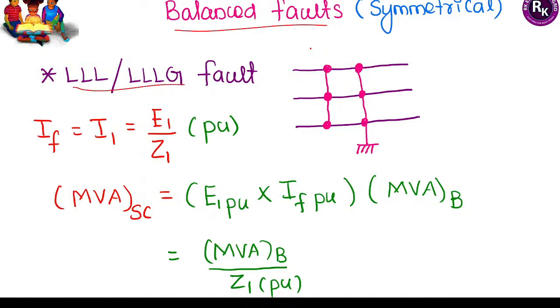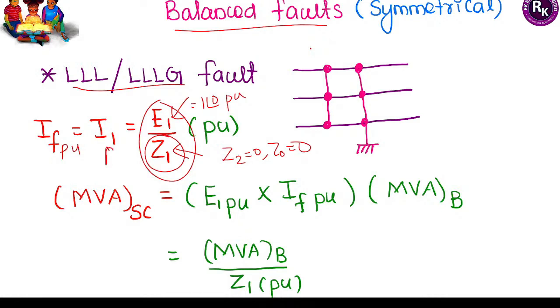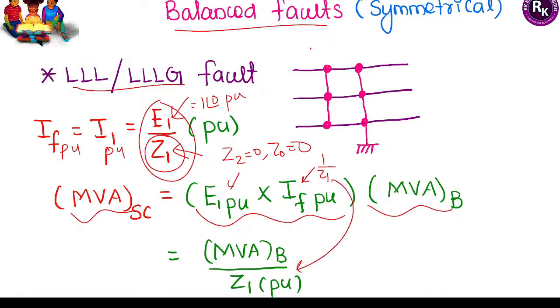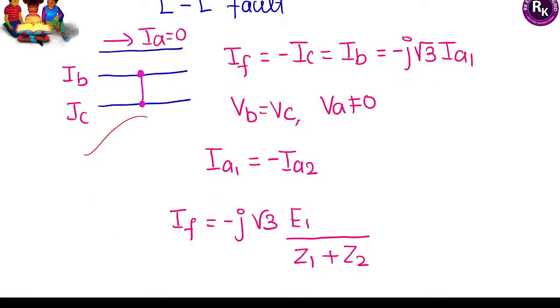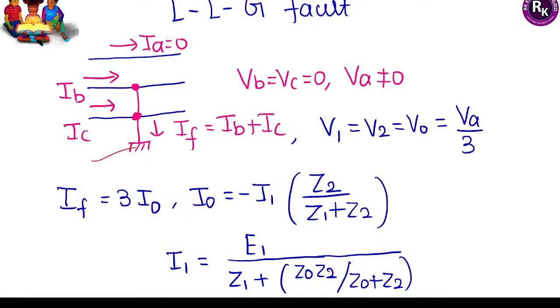For balanced (symmetrical) fault: only positive sequence component exists; negative and zero sequence components are zero. Pre-fault voltage is 1 ∠0° per unit. Fault current (positive sequence current) equals pre-fault voltage divided by positive sequence impedance. Short circuit MVA = per-unit fault current × base MVA = (1/Z1) × base MVA. For unsymmetrical faults: pause and note the boundary conditions for line-to-ground fault, line-to-line fault, and double-line-to-ground fault — all conditions are written in detail.